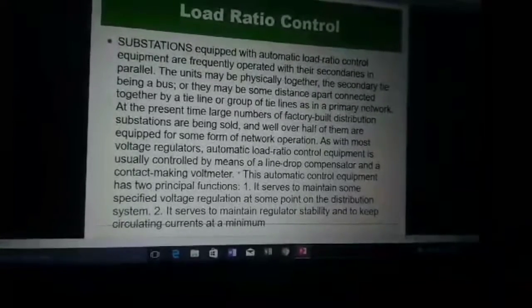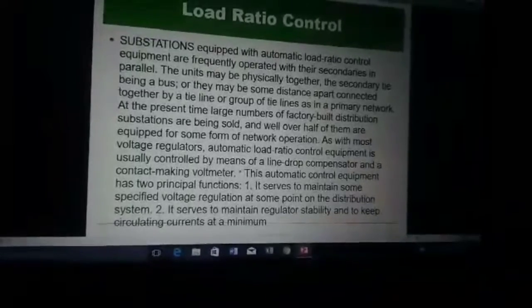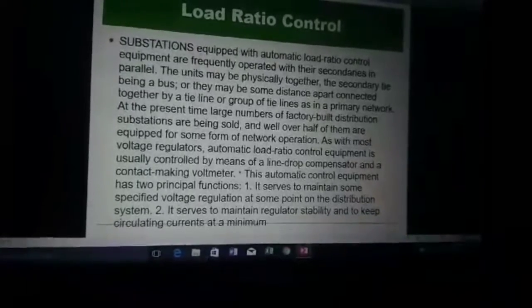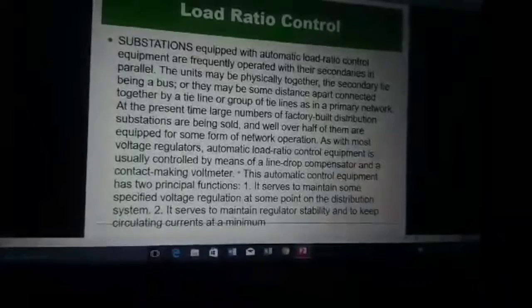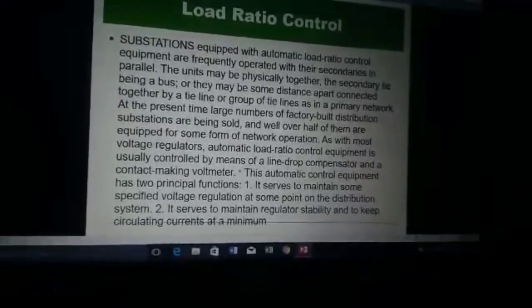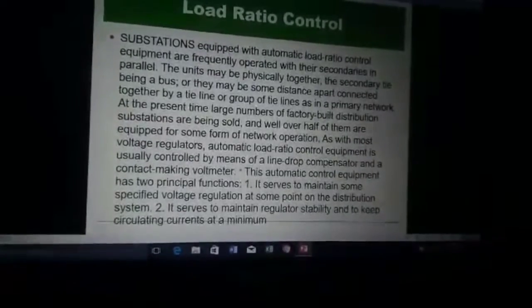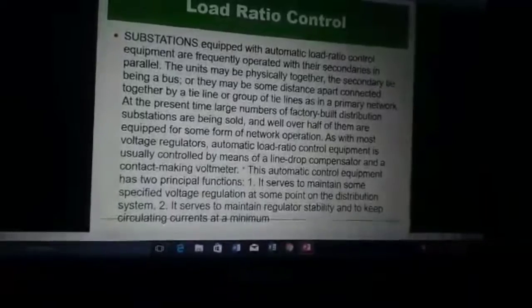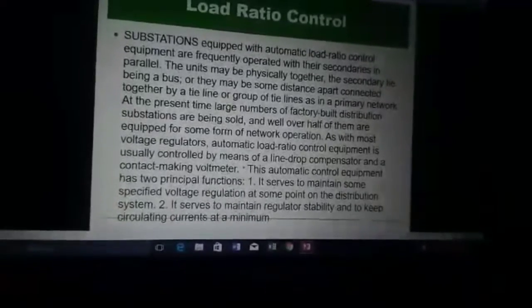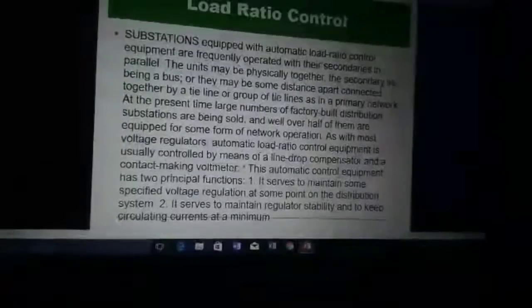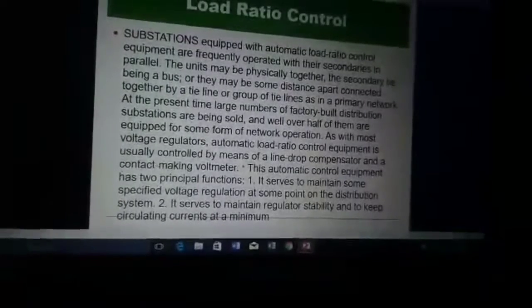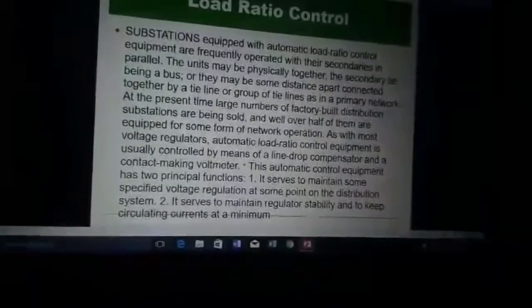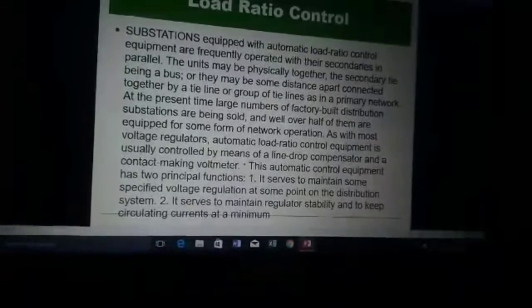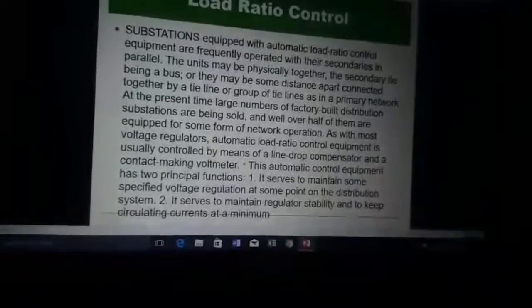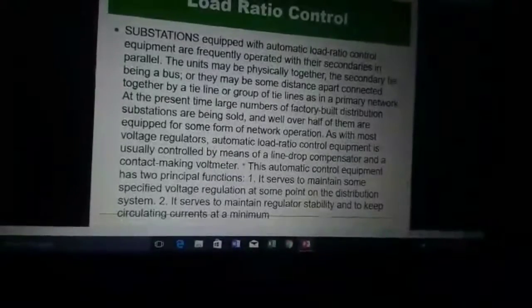As with most voltage regulators, automatic load ratio control equipment is usually controlled by means of a line drop compensator and a contact-making voltmeter. This automatic control equipment has two principal functions. First, it serves to maintain some specified voltage regulation at some point on the distribution system. Second, it serves to maintain regulator stability and to keep circulating currents at a minimum.